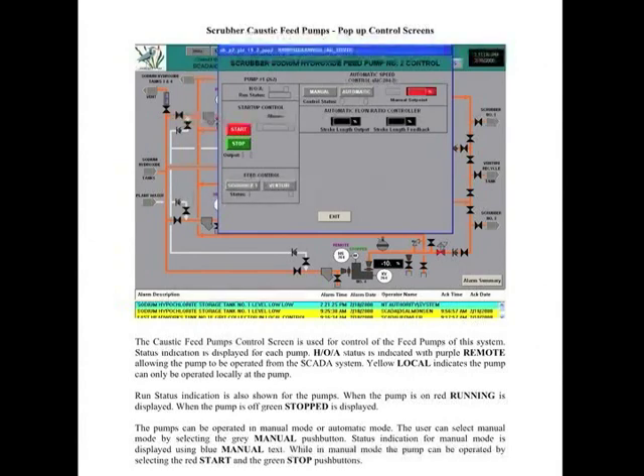On these pumps you have start-stop capability, again in manual mode. If you put it in automatic mode, you will have lead lag set up. It's not shown yet on these drawings, but it will be. If you're having 2 different pumps go to your Venturi, you can have one set as the lead and one set as the lag, and as it needs to bring on the pumps to keep the alkalinity or to keep the pH up, it will turn them on and off as it needs to.